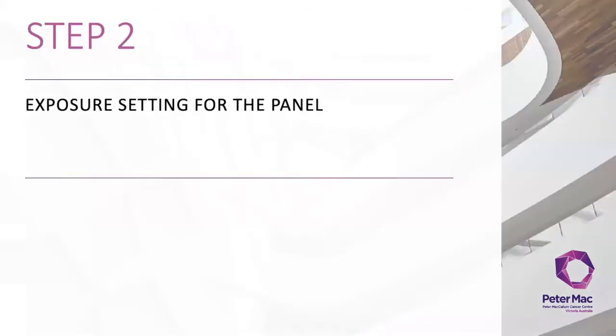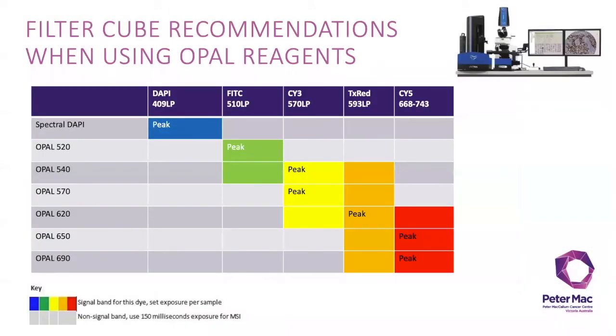The next step is to set your exposures for each slide. The table on this slide shows the exposure recommendations for each of the opal fluorophores. The signal bands for DAPI and each of the opal fluorophores are shown by the colored boxes. When imaging a monoplex slide, say with opal 520, you only need to auto expose in the FITC channel.